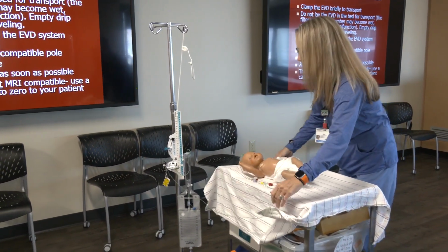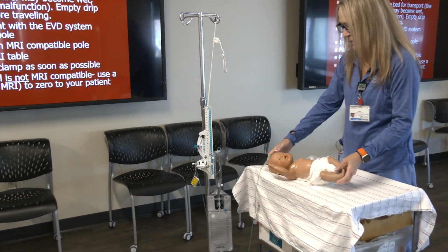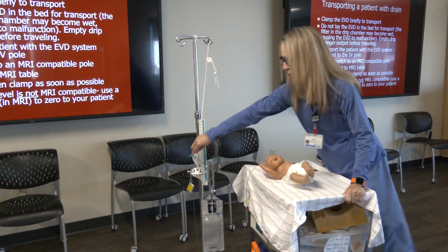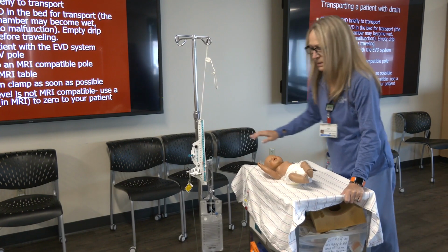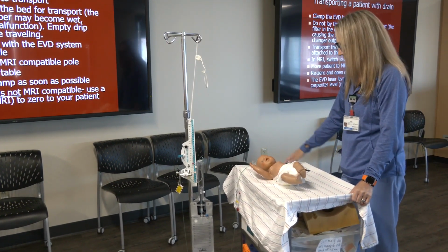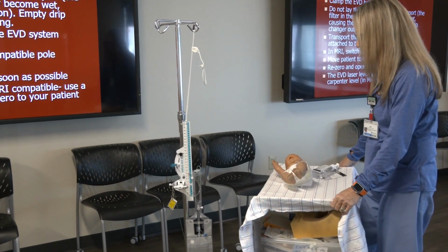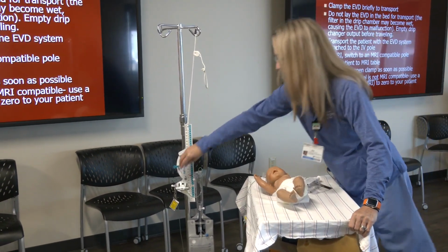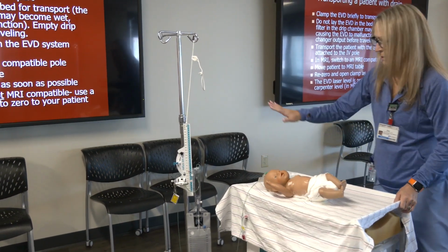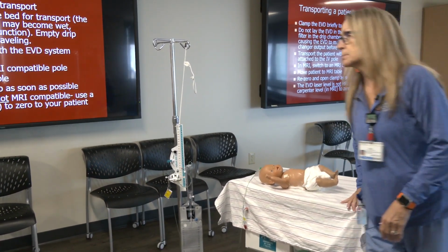And then you can unclamp it while they're in there, because you're going to re-zero. Like, put them on this table, you'll re-zero to the tragus so that you can open this up while they're getting their scan, because if they're having trouble, we don't want to leave them clamped all that time. So you'll leave it open after you've already checked where they're at, and then when you come back out and you're going to move them, you clamp it off to the patient again, and then you'll go back to the room and re-zero them and set everything back up in their patient room.